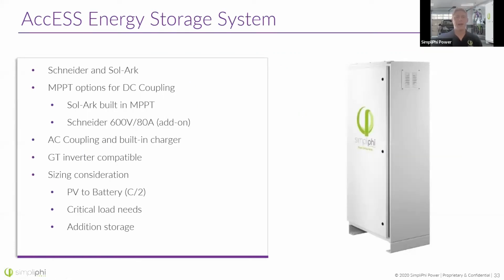All right, and our Access units. So our Access units, it's a NEMA 3R rated outdoor ready cabinet that's able to stand up to harsh weather conditions. This comes either AC or DC coupling, so you can get a Sol-Ark 12K inside that comes ready to be AC or DC coupled, or you can get a Schneider XW Pro, and even you can add on a 600 volt Schneider charge controller if you need. These are going to come with frequency shifting and the newest grid-tied inverter compatibility. So if you're installing brand new equipment with this, it shouldn't be a problem.